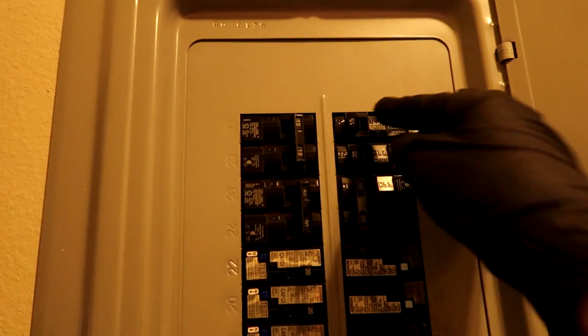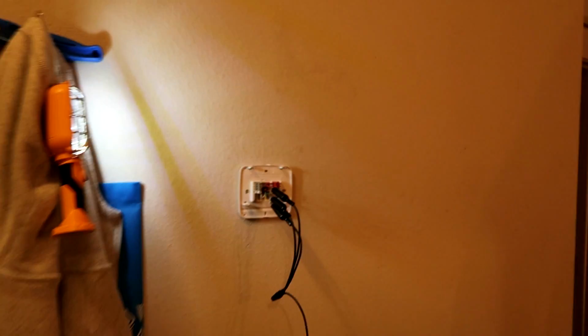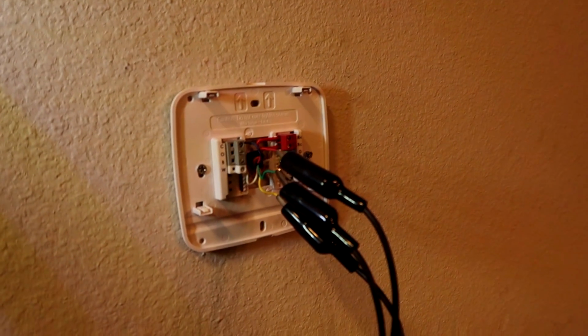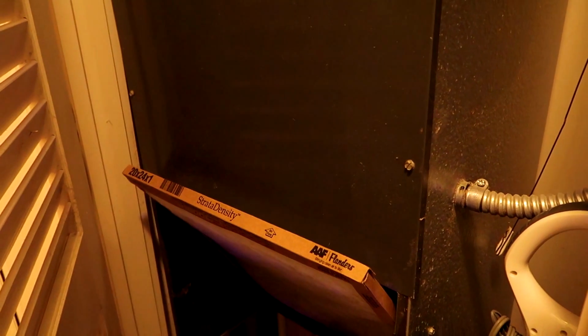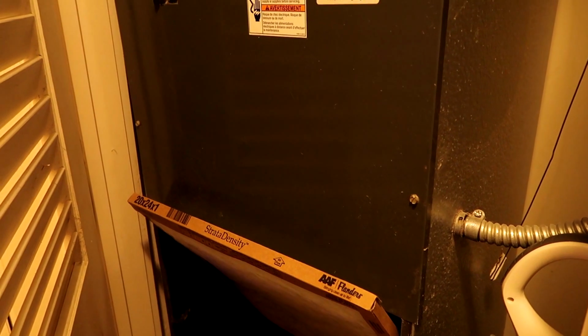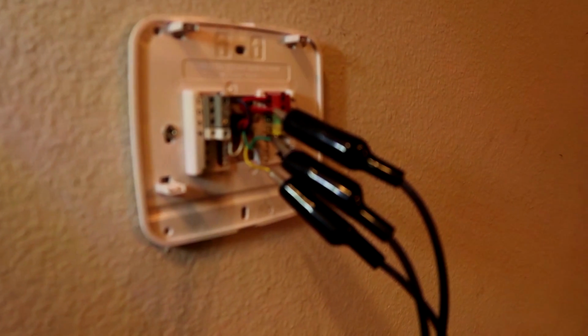So I'm going to turn the power back on and let's see what happens. Let's see. Nothing. I'm wondering if the fuse popped now. Meaning, bad contactor. I got everything jumped out. It should be coming on. It came on immediately when I just had the red and green, but since I threw the yellow in there, it's not coming on. So I bet it popped the fuse.